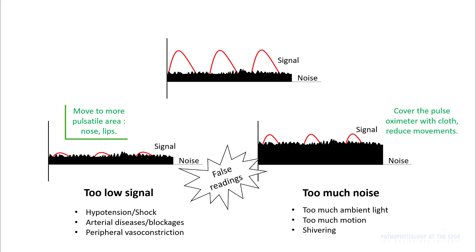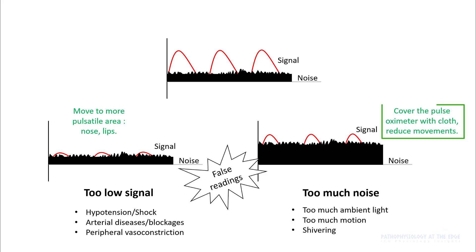To improve readings, move your pulse oximeter to more pulsatile areas — for example, the nose and lips — reduce movement, and remove ambient light.